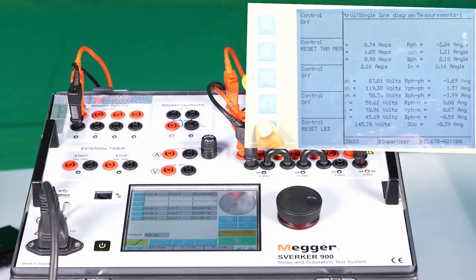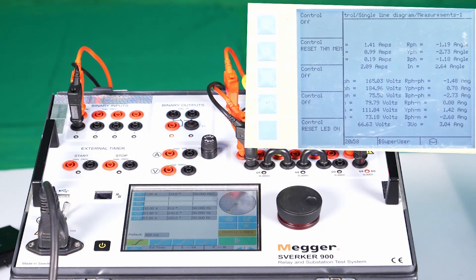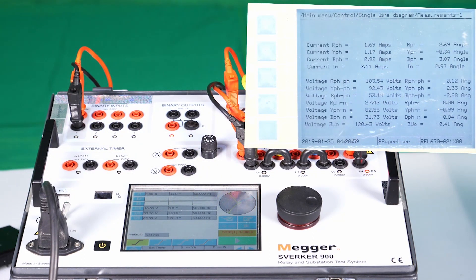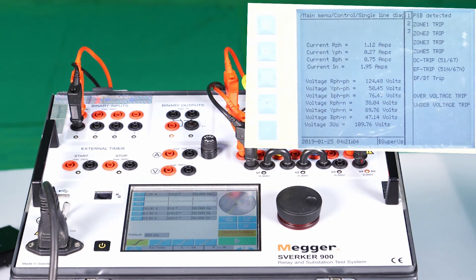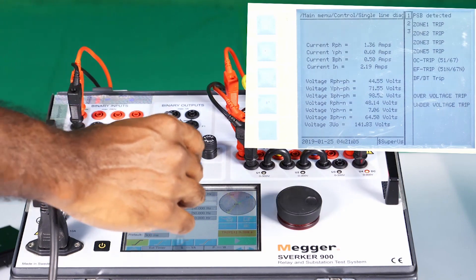Let me verify the result in the second region. I will reset the relay. Now I am going to verify the 220 degree boundary, starting from 218 degrees.